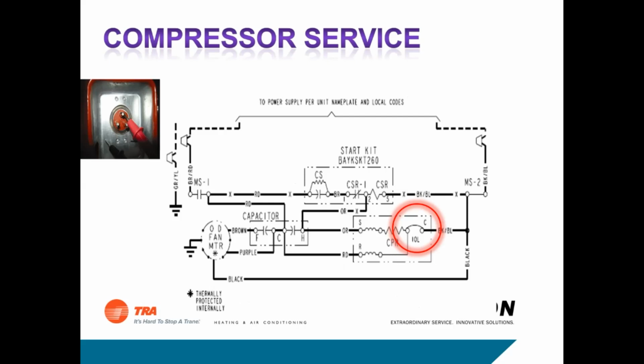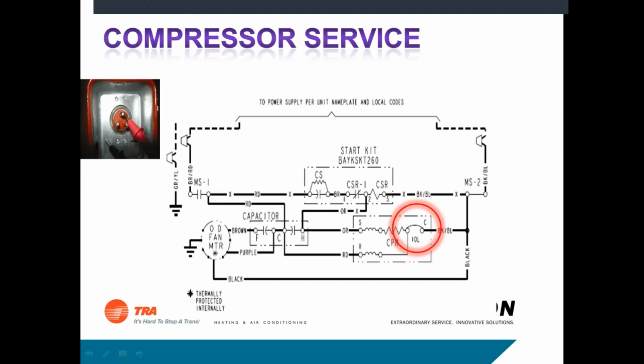What I've got here, this is how to test. We kind of went over this. It's how to check the voltage and check the ohms on a compressor to make sure the compressor is working properly. So what this is showing is, that's your overload. The circle here is your overload in the compressor, and this is internal to the compressor.